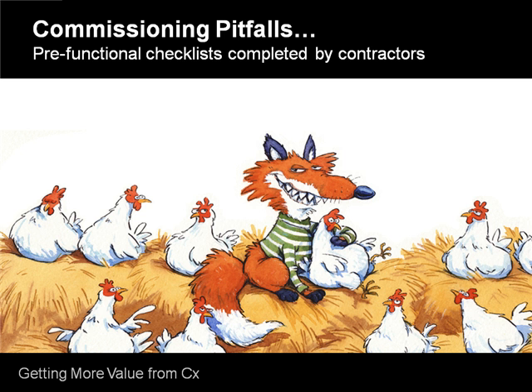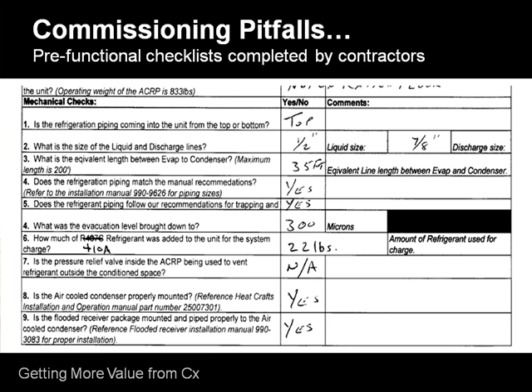And so we've had problems where we've had pipes buried in walls that were hooked to the wrong spot, past balancing, and they passed. And yet when we went to commission it, we couldn't get the cooling coil across. We find it piped across the chiller, not across the pumps. And this was just an excerpt that we handled from a pre-functional checklist. So my understanding is, George, oftentimes you will issue as the commissioning agent the pre-functional checklist to the contractor. The owner will have them fill it out.